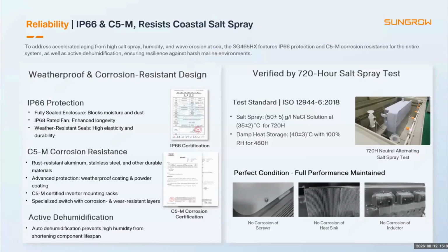The SG510HX is designed for harsh environments. It provides IP66 protection and C5M corrosion resistance, together with active dehumidification. The design has also been validated through salt spray and damp heat testing. This improves long-term reliability in coastal, humid, and dusty environments.